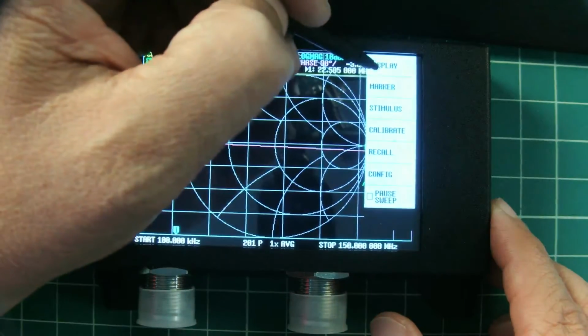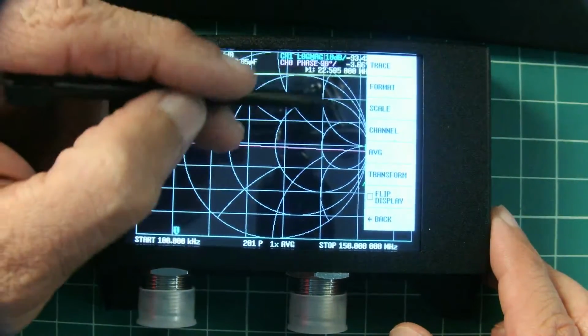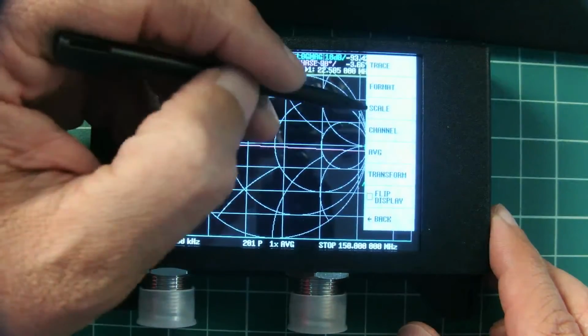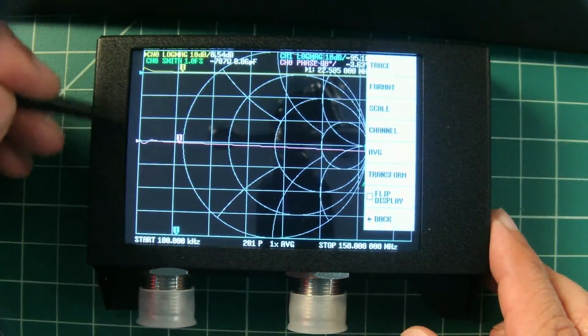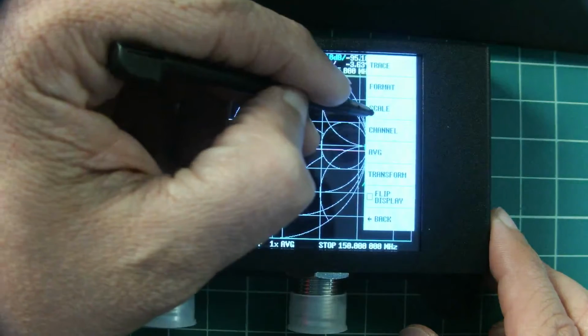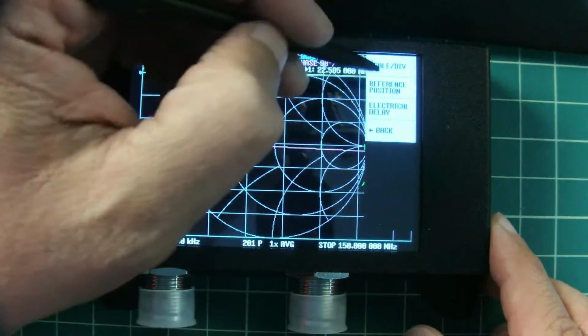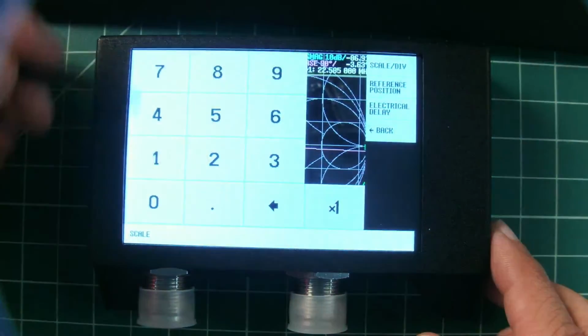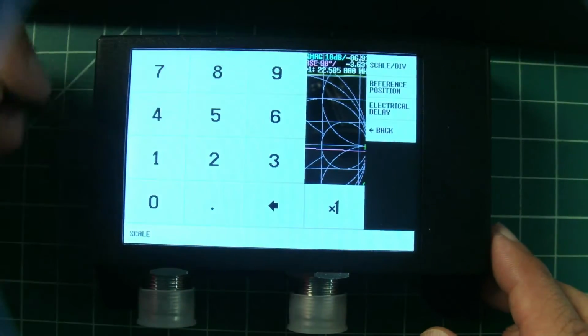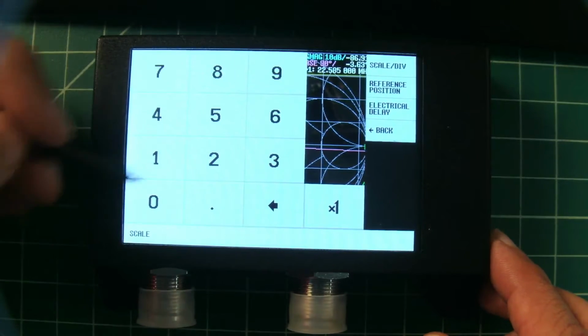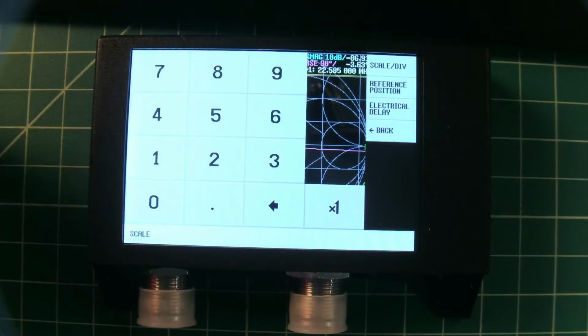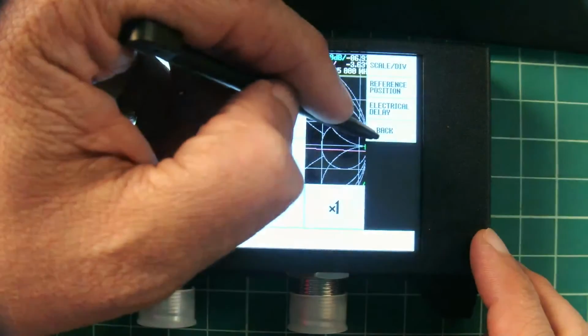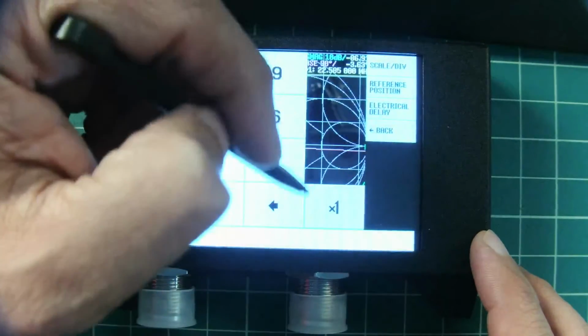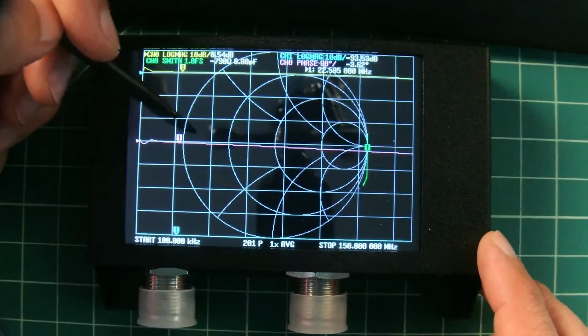Okay, another thing I want to do is go back and talk a little bit about the display. So when I click display, I get a couple of options: trace, format, scale. Scales, you have a certain amount of squares here. So if I go ahead and click scale, one of the things I can do is adjust my scales per division. And I can set the value. I believe the default value is 10 counts per division, and I can move this up and down depending upon the granularity of the sweep that I'm doing. I'm just going to leave that as is. And I wanted to point that out just for reference.